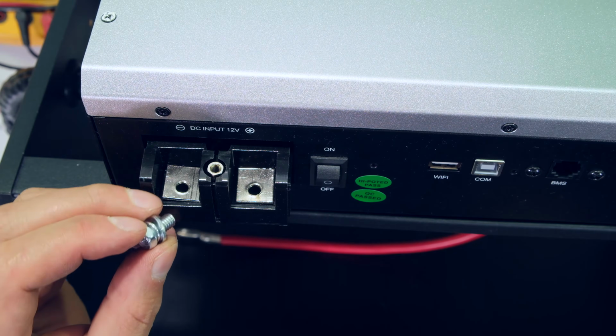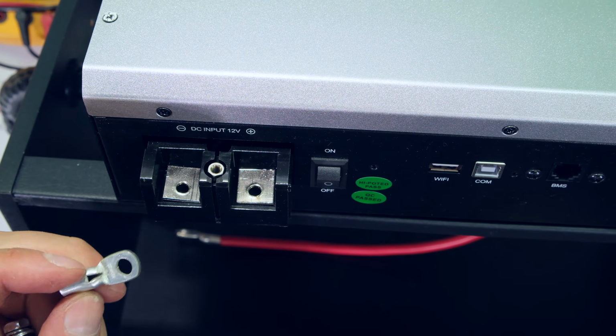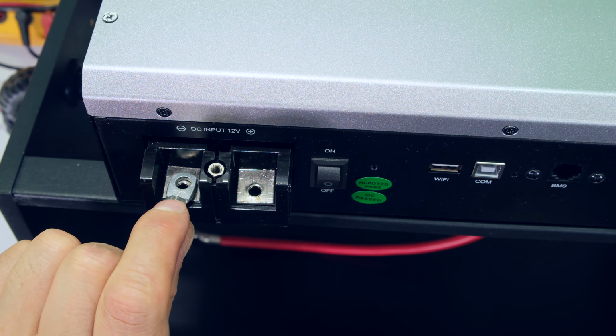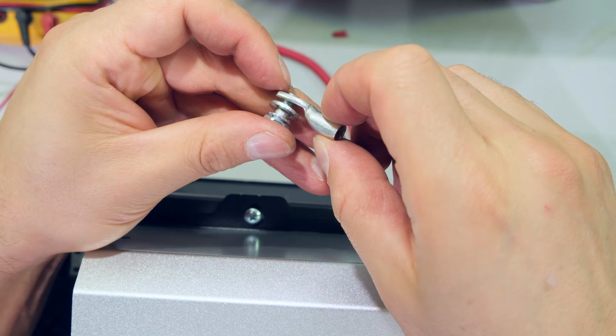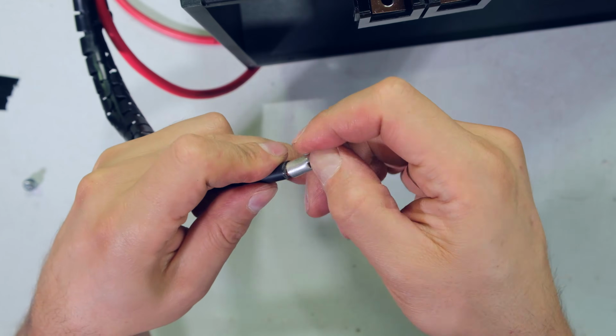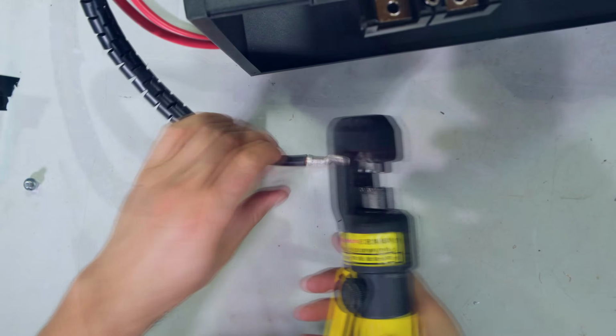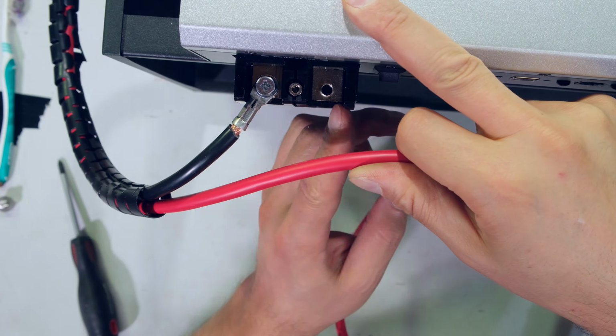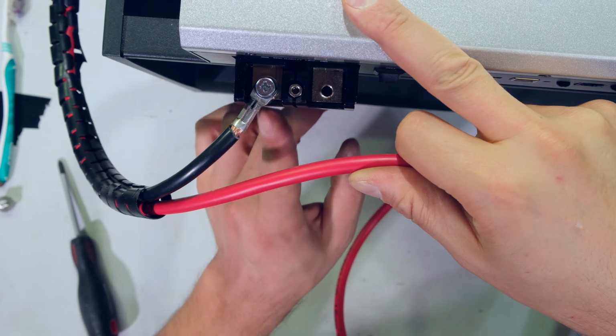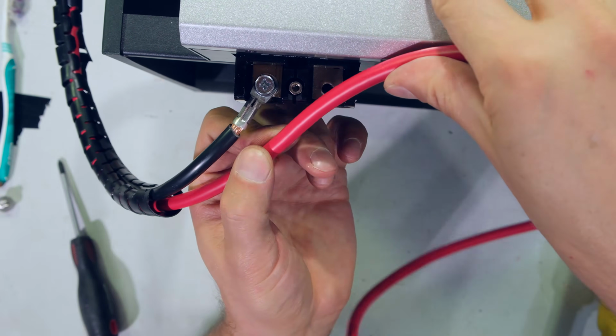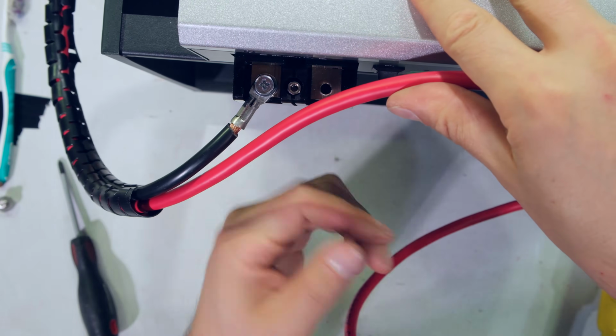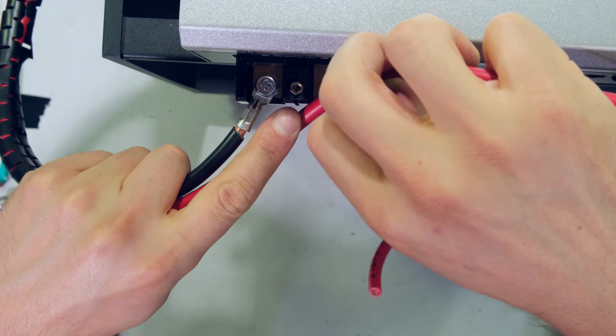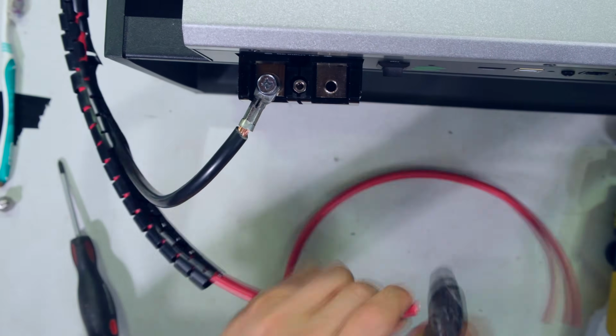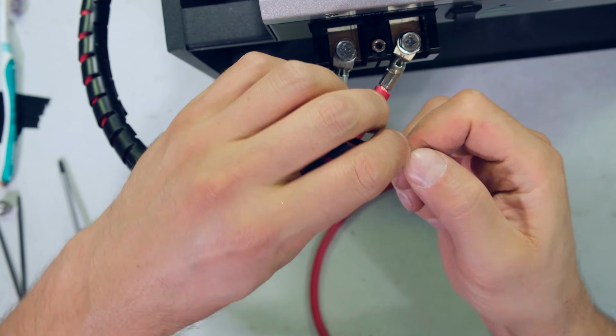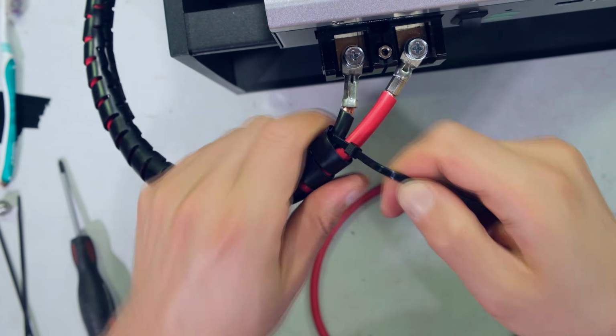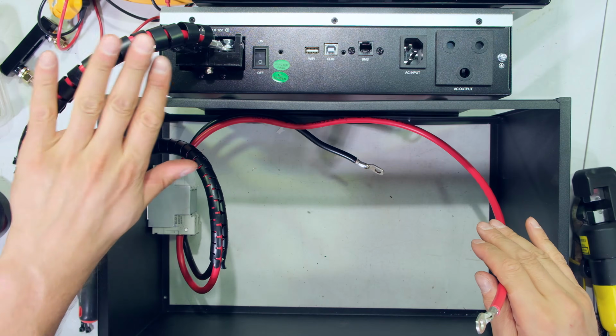Now on the inverter terminals, I also have a screw mount, which means that I can still use a lug. So there we go. It's going to be like that. Right, so I'm just sizing this up. The screw here is 6mm. Right, so I'm just fitting the lug now. When I'm dealing with thicker wires that are joined to terminals that are slightly offset, I only fit the one and then I measure up the other one. Otherwise, we find that the fly lead here is going to be all deformed. So now I can measure this up. Yes, that's right. I'm just putting a cable tie here. Right, so from the circuit breaker, it goes to the inverter.